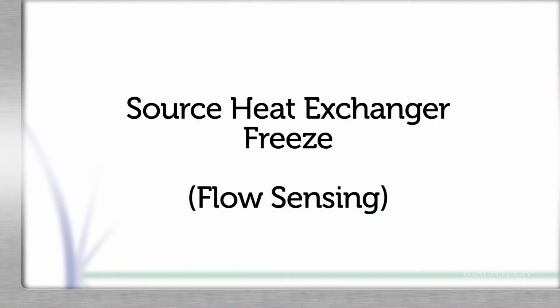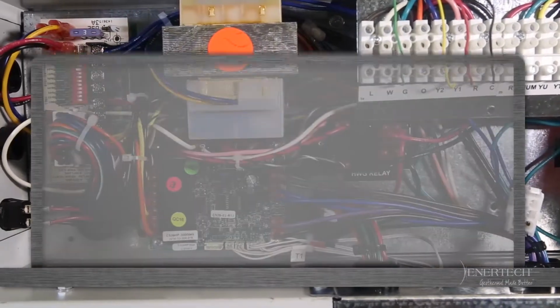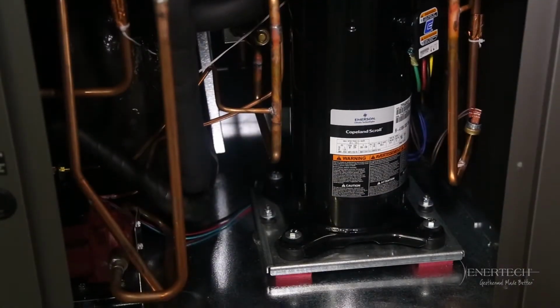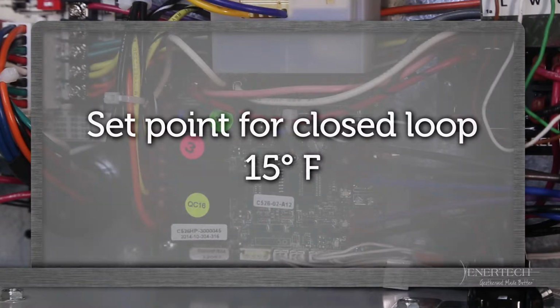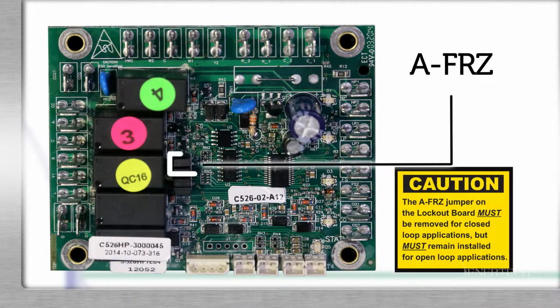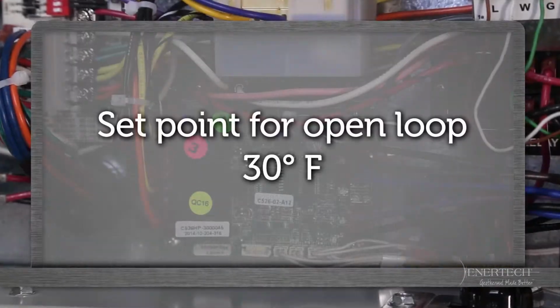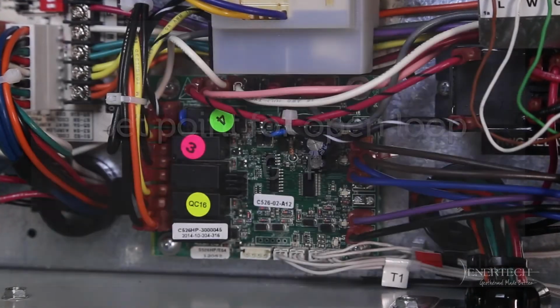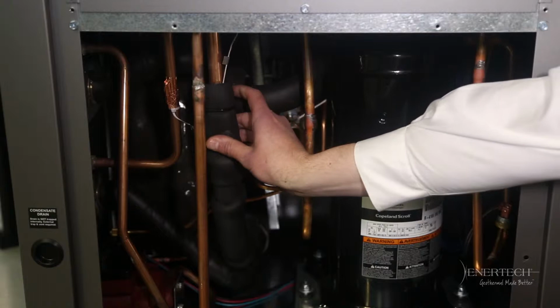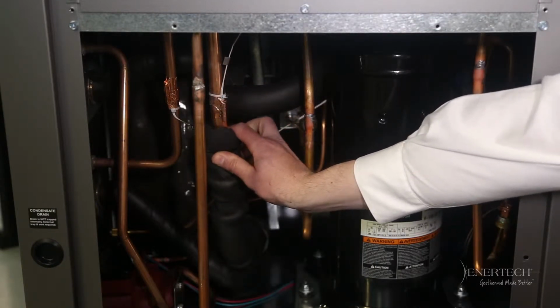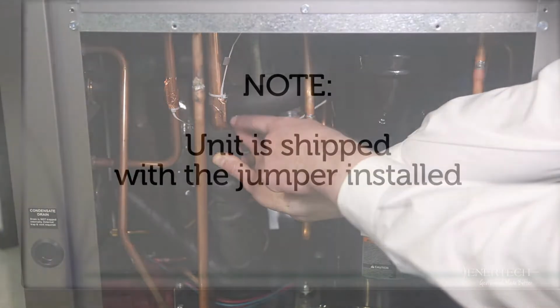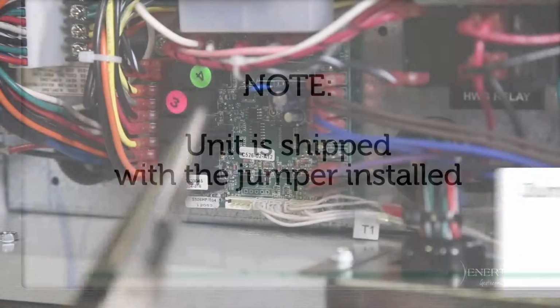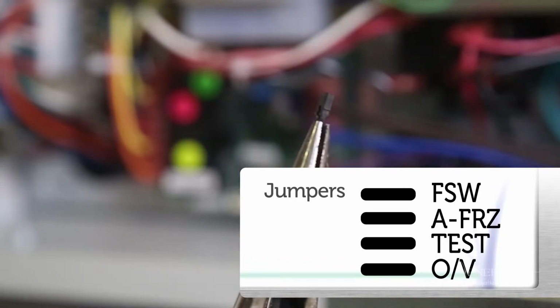When in heating mode, if the source heat exchanger is lower than the set point for 30 continuous seconds, the compressor operation will be interrupted and the control will go into fault retry mode. This is important. The set point is 15 degrees for closed loop with the A-FRZ or A-freeze jumper removed and 30 degrees with the A-FRZ jumper installed for open loop. At startup, the sensor is not monitored for 30 seconds to avoid nuisance faults. This sensor is located on the refrigerant line in between the source heat exchanger and TXV, refrigerant inlet of heat exchanger in heating mode. Note, the unit is shipped with the jumper installed. It is important to remove the jumper for closed loop applications.